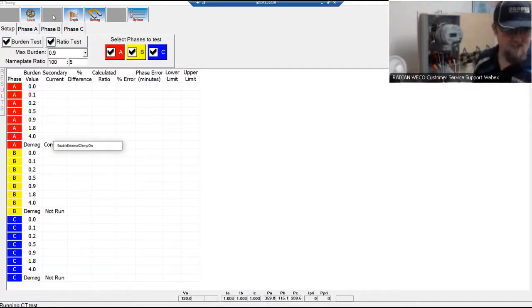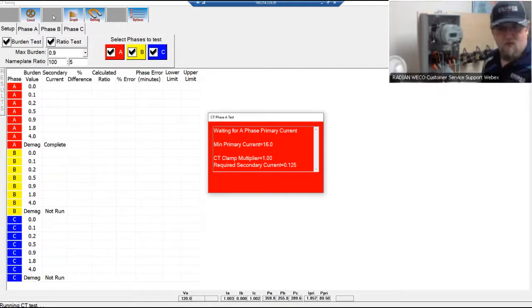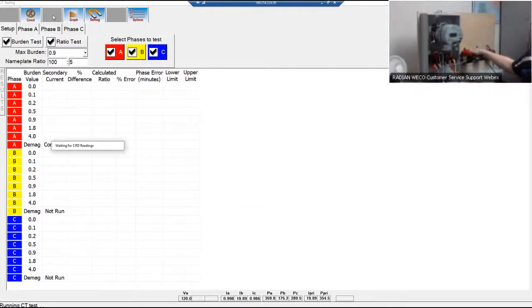When you start your test, it's going to call for the CT, make sure it sees a CT probe. And now what it's going to do is wait for primary current to be read by the RW. Now wait for A phase primary current. What it's waiting for is 80% of the read secondary, so in this case, 16 amps. With that knowledge, I can then go ahead and put this over my CT A phase primary. That message will go away and it'll start your test.